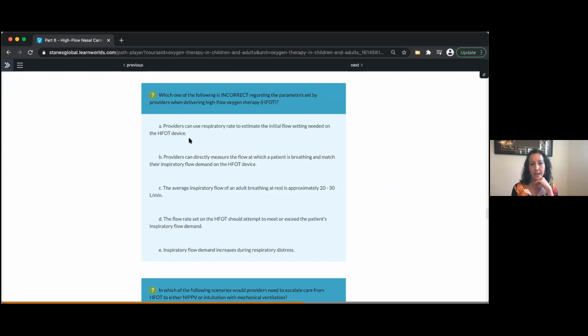So we can, as providers, use the respiratory rate just to estimate the initial flow setting needed. And the average inspiratory flow, as you've mentioned, Shelley, is 20 to 30 liters per minute just breathing at rest. So when you're setting up your high flow oxygen therapy device, what flow do you normally start with? Well, we know that the max flow on some devices is 40 liters a minute, and others is 60 liters a minute.